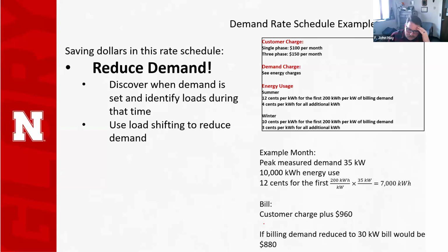So I did a version of it. We're back in the lower right-hand corner here. In this case, I have an estimated peak measured demand of 35 kW. I use 10,000 kilowatt hours. So I'm going to pay 12 cents for the first 200 kilowatt hours times 35, for the first 7,000 kilowatt hours. They're basically saying if I have lower demand, I would actually pay that higher rate of 12 cents for fewer kilowatt hours. That's the second half of my month when I'm using kilowatt hours above that value, where I'm paying less. So in this case, the customer bill with this value is $960.